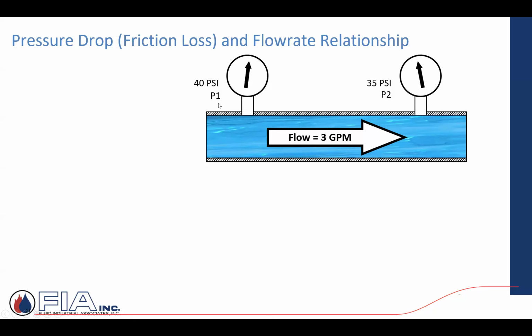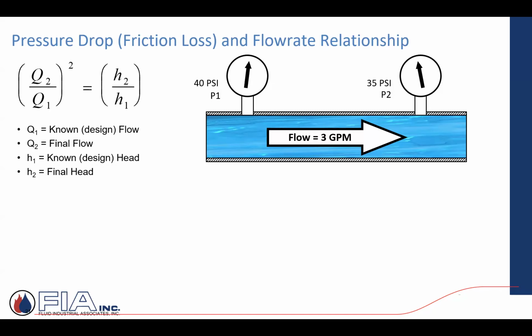There is this inherent relationship between the change in flow and the corresponding change in pressure drop based on this calculation that we're going to jump into right now. There's a relationship. When you have a known flow rate and a known pressure drop, when you change that flow rate in that given system based on the original flow, which means you calculated the original pressure drop, in this example, 3 gallons a minute at a 5-pound pressure drop.